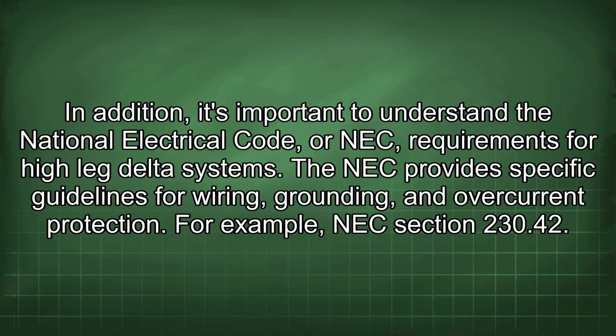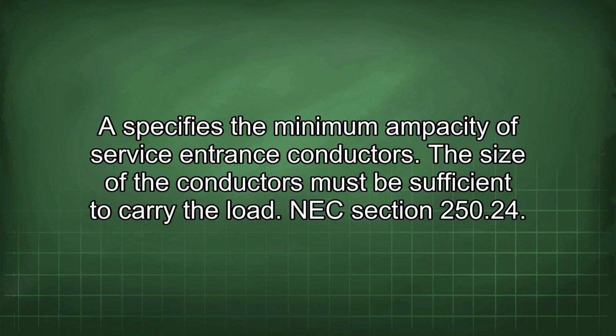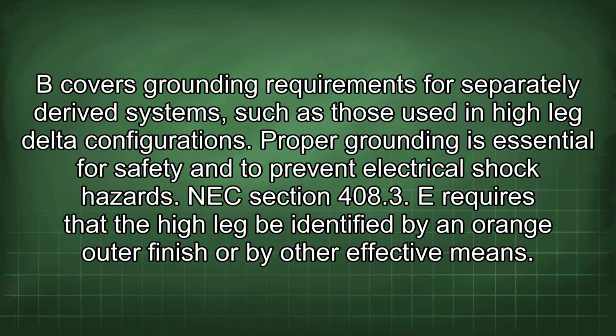In addition, it's important to understand the National Electrical Code, or NEC, requirements for high-leg delta systems. The NEC provides specific guidelines for wiring, grounding, and overcurrent protection. For example, NEC Section 230.42 specifies the minimum ampacity of service entrance conductors. The size of the conductors must be sufficient to carry the load. NEC Section 250.24 covers grounding requirements for separately derived systems, such as those used in high-leg delta configurations. Proper grounding is essential for safety and to prevent electrical shock hazards.